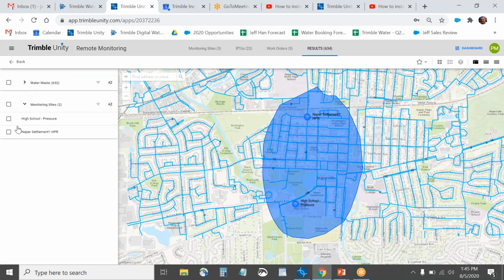I want to take these two monitoring sites and view the measurements to compare them together. I have the ability to stack multiple pressure recording sites on top of one another, so it's easy to see if an impulse or water hammer at a certain time was also seen at another site, helping me isolate where it might be coming from. I can also look at my GIS to see other assets in the area, like pumping stations, that could contribute to this impulse.